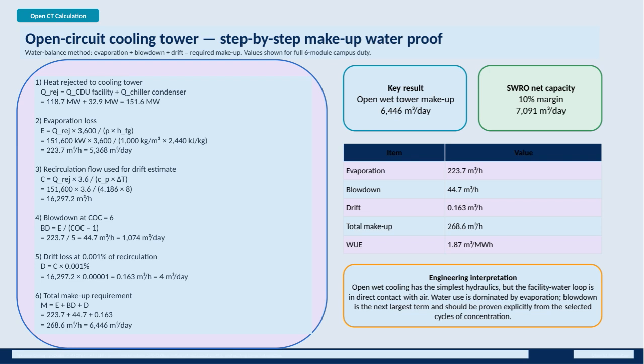Blowdown is then calculated considering a cycles of concentration of 6, giving us about 44.7 cubic meters per hour. Drift loss, although much smaller, is computed as 0.001% of the recirculation flow, which equates to roughly 0.163 cubic meters per hour. Adding these components together, the total makeup water requirement comes to approximately 268.6 cubic meters per hour, or 6,446 cubic meters per day. To ensure reliability, a seawater reverse osmosis system with a 10% margin is sized at about 7,091 cubic meters per day.